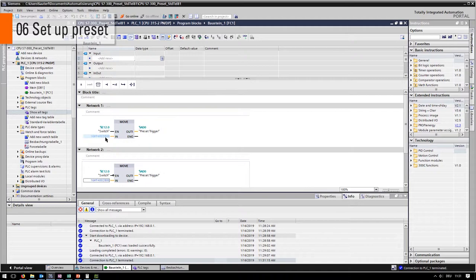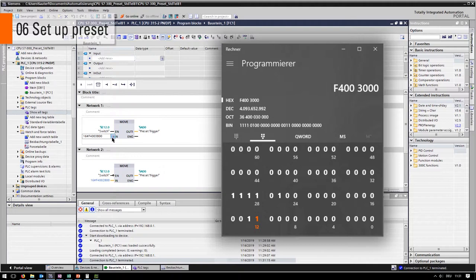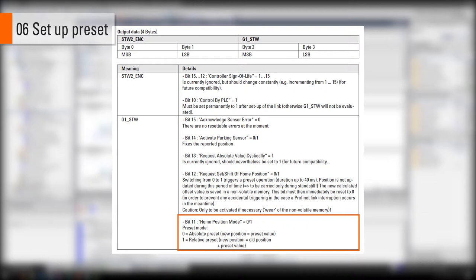Type in the hex value as shown in the picture. Do the same on the second move block. If we look again on the telegram structure, we can see that bit 11 is now set to 0. This activates the absolute preset function.